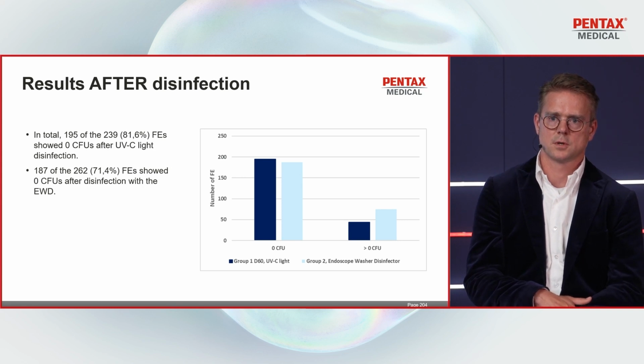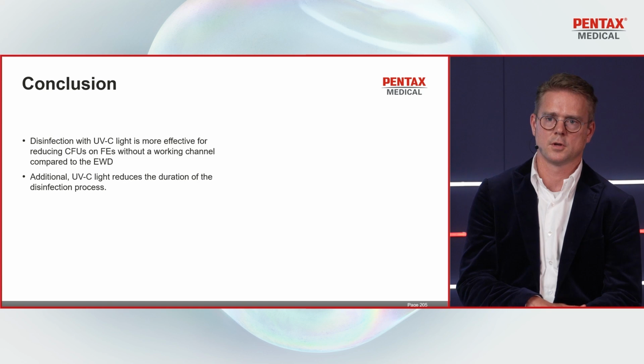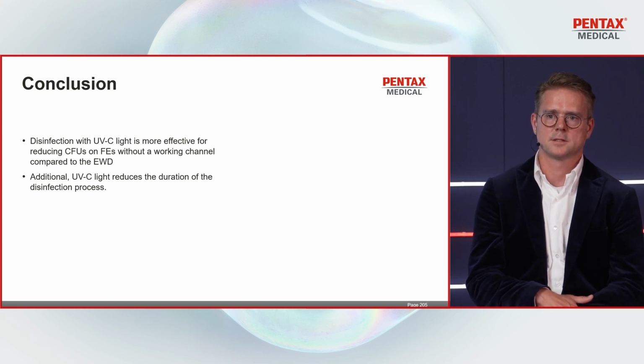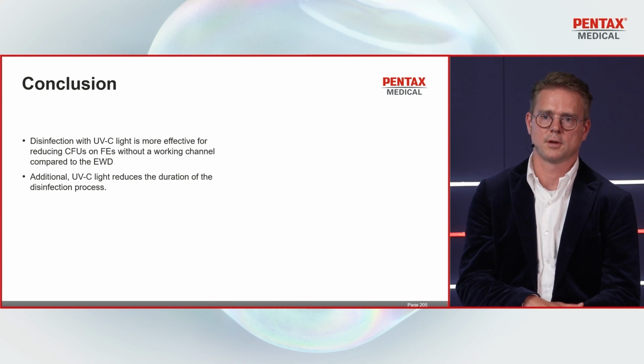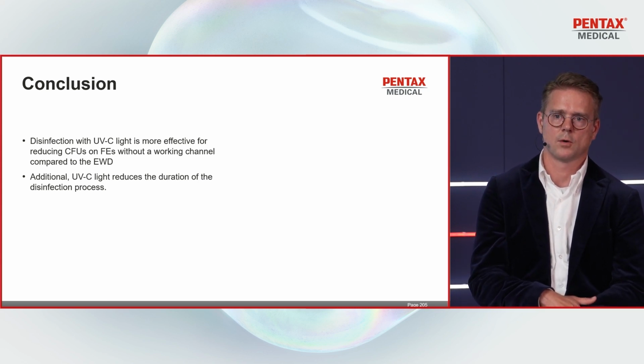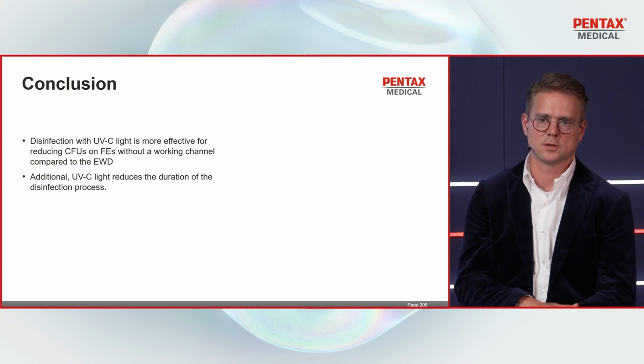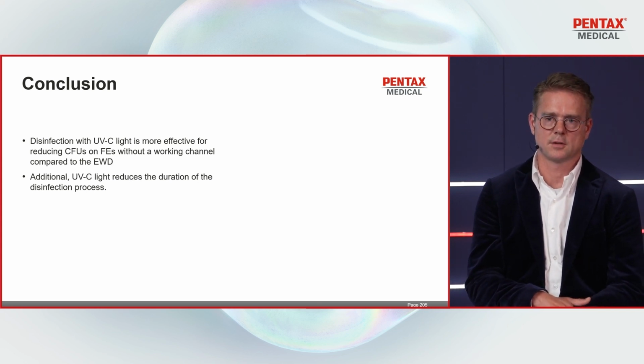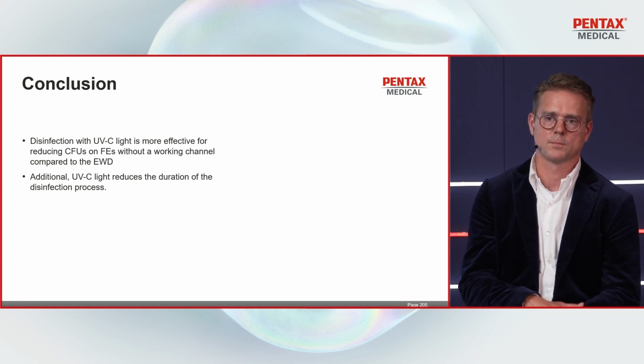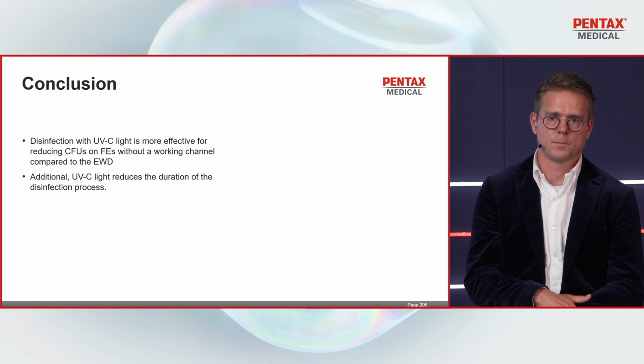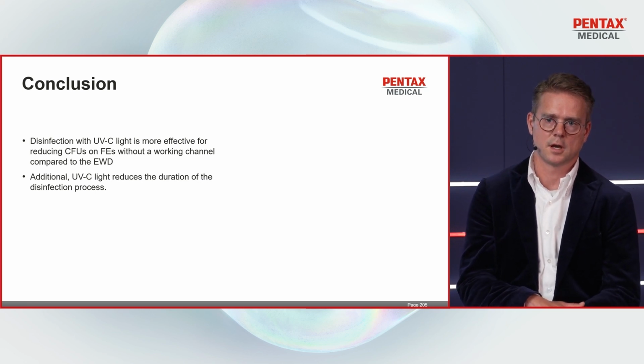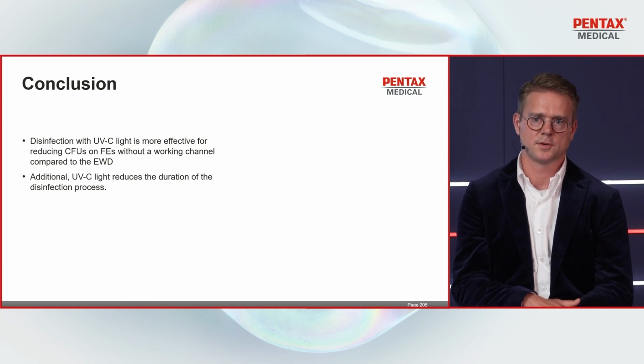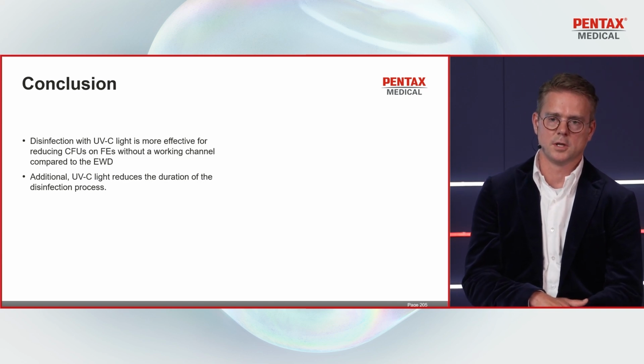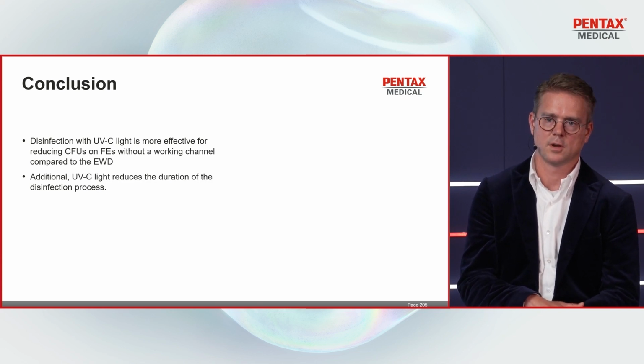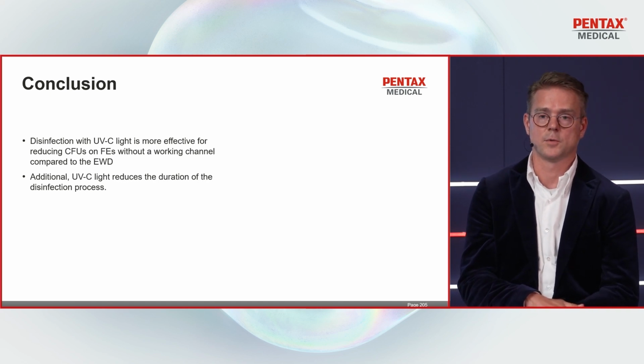So there was a good result for the UVC light method, and that was therefore more effective in reducing the CFUs on the flexible endoscopes without a working channel compared to the washing disinfector, which uses water and chemicals. Another thing that we notice, of course, is that the UVC light method reduces the duration of the disinfection process, which might be an additional advantage in the ENT practice. Well, thank you for your attention.